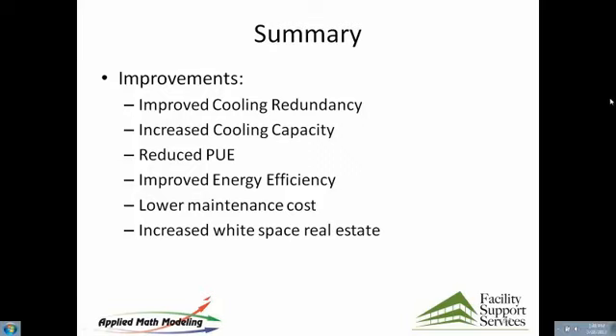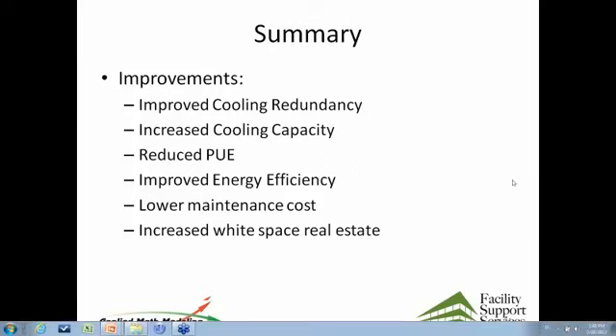Okay. So with all the improvements and trying to get the customer the most cost-effective pricing that they can, what we were able to achieve was improved cooling redundancy. By getting the airflow back in the floor, not leaking out through behind the racks, we were able to get into an N+1 capacity, and then they could shut a CRAC unit down. We have increased cooling capacity. If they wanted to go with an N system, they have more room to expand. We were able to get their PUE reduced, which ultimately returns lower maintenance costs and operating costs, and it's just all around small changes have big impact. Yep.